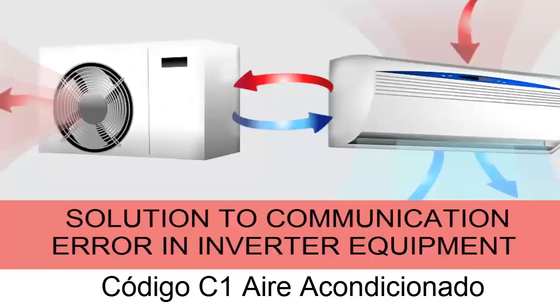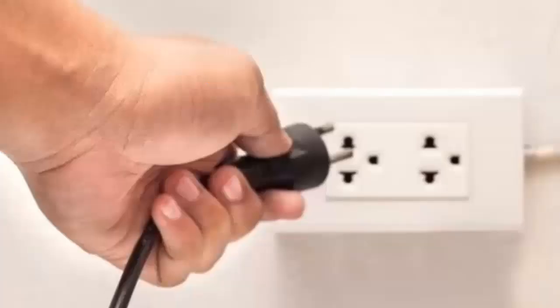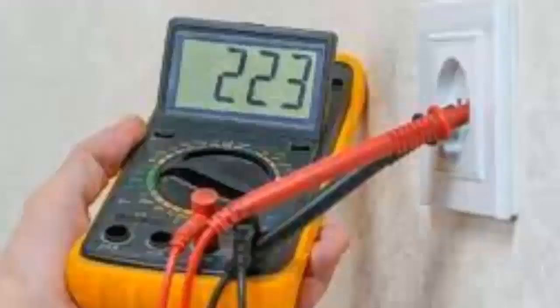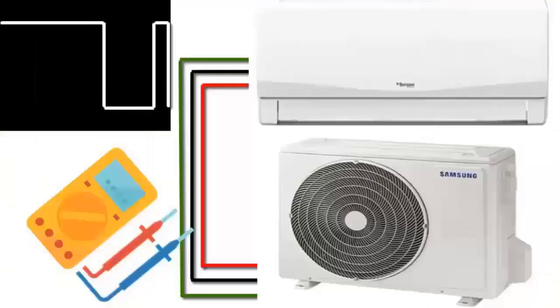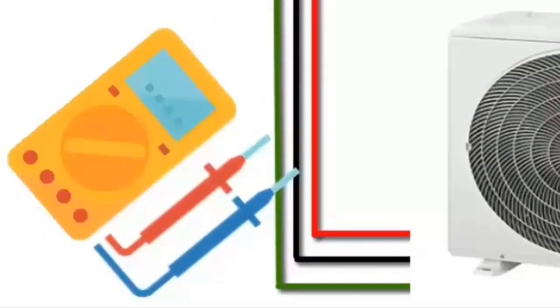Possible solutions: A. Disconnect the equipment and reconnect it to see if the problem persists. B. If the problem persists, use a multimeter to check the voltage supply from the external source. C. Check the connections of the communication cables. D. Using a multimeter on the DC voltage scale, check if the signal voltage is constantly changing — use the signal and neutral cables to take the measurement. E. With a multimeter, check on the electronic board if the optocouplers in the signal circuit are working correctly.